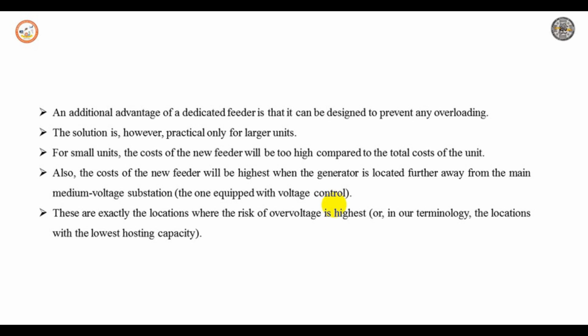Building a new rural distribution network completely based on cable might even result in a significant reduction in the hosting capacity. The lesser voltage drop per unit length allows longer feeders, with the boosting point located further away from the main substation. The minimum over voltage margin is independent of the feeder. So with cables, the point is further out along the feeder where the source resistance is higher, and thus the hosting capacity will become small. The hosting capacity is also increased by shortening the feeder. The main cost associated with this is that more transformers and more substations are needed. This is about new or stronger feeders. So let us move on to the alternative methods for voltage control.